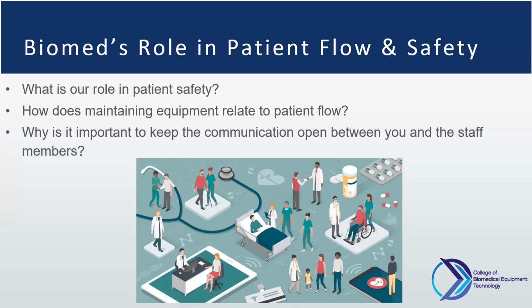For me, I think why it's important to keep the communication open is just so that you're aware ahead of time of what's going on and it helps you plan ahead. Yep. So if we go back to that CT example, if we have to order a part for a CT scanner because it's down, and you tell them that the part is coming in on Monday, but it ends up coming in on Tuesday, they may have booked patients for Monday. And so not only are you disrupting flow because that open communication isn't happening, that, hey, the part's going to be delayed, you want to make sure that open communication is happening so that patients are able to get the care that they need.